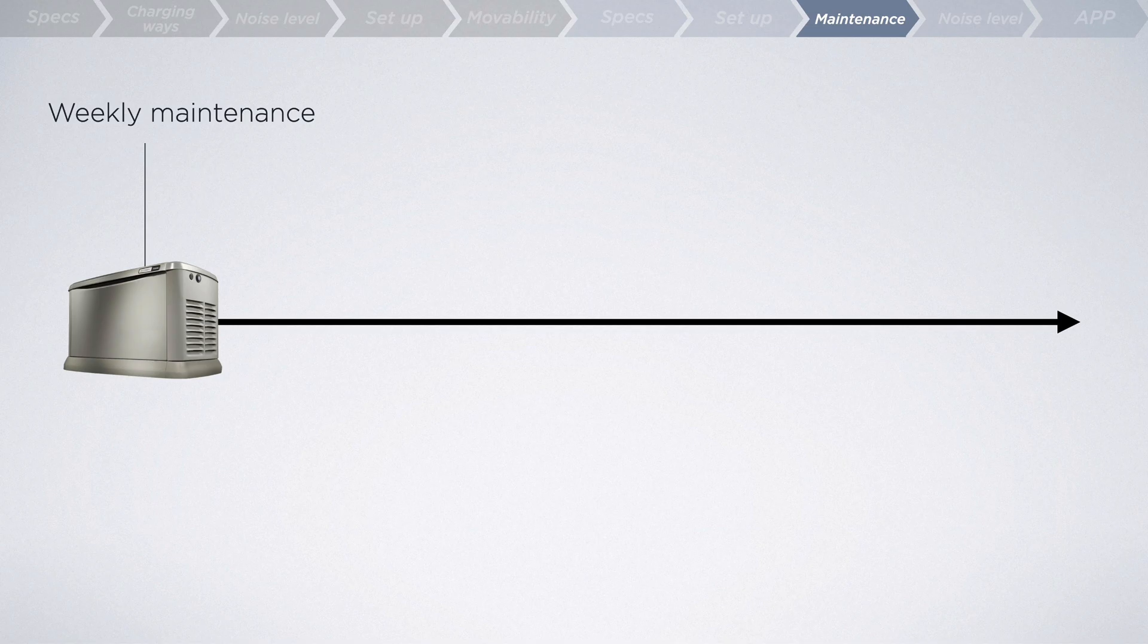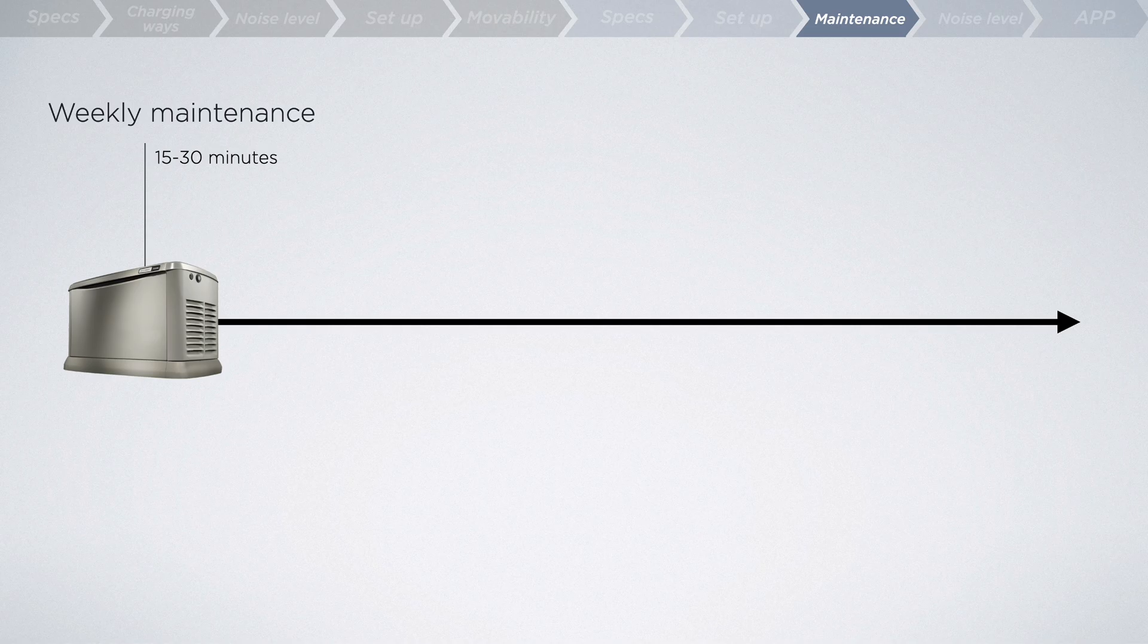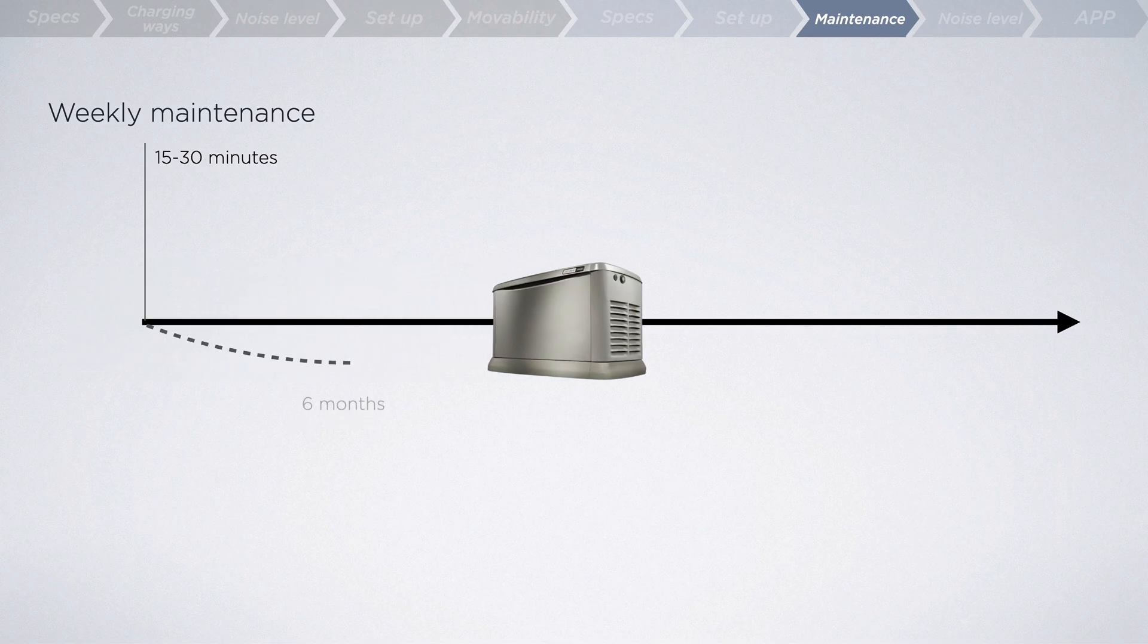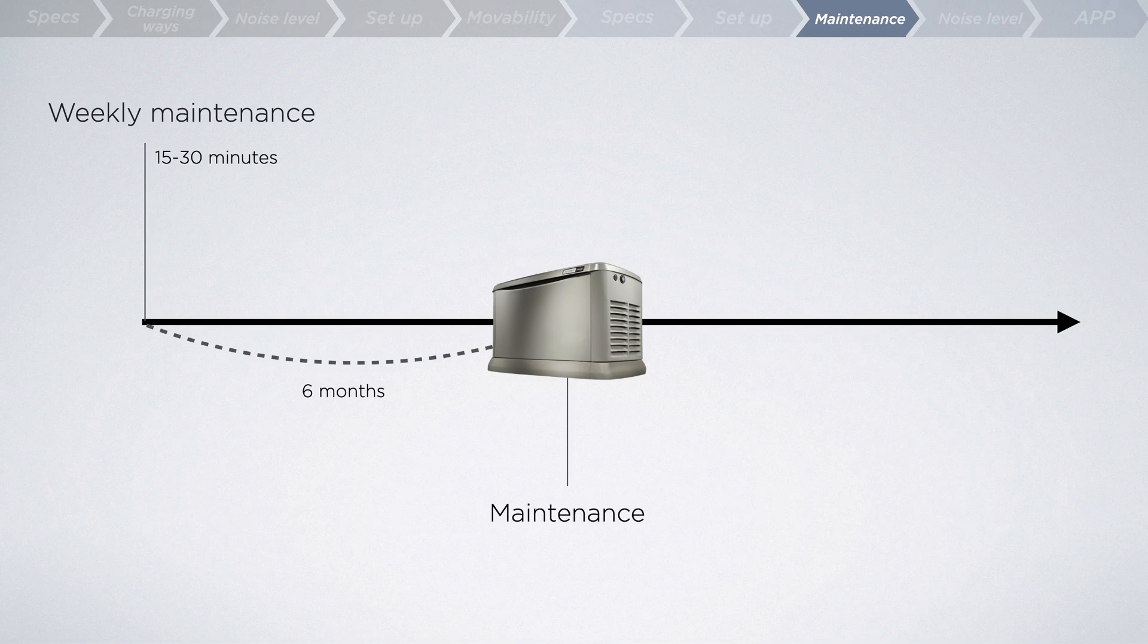Let's delve into ongoing maintenance. It's recommended that your generator should be programmed to exercise for at least 15 to 30 minutes a week to ensure it'll start up in the event of an emergency. Besides, routine maintenance should be performed every six months or after 200 hours of operation, whichever comes first.